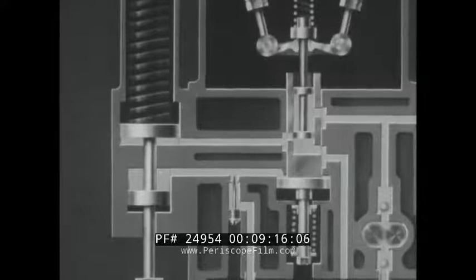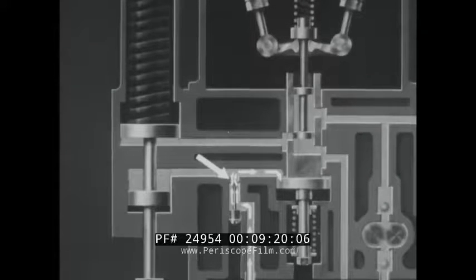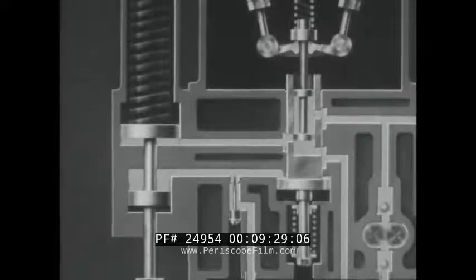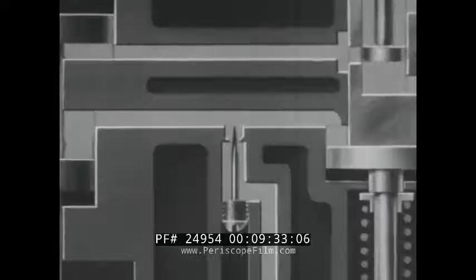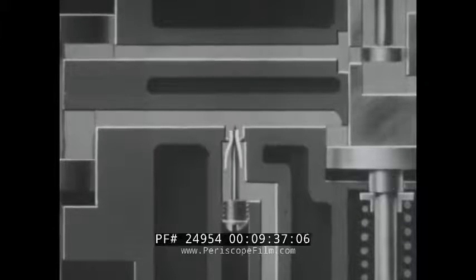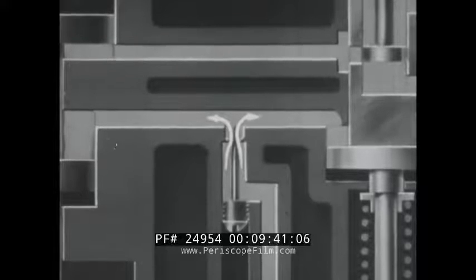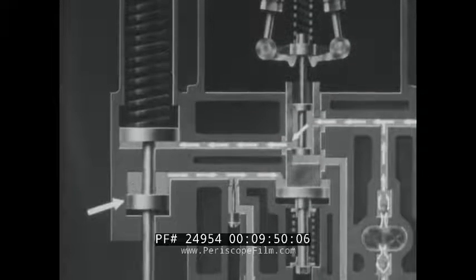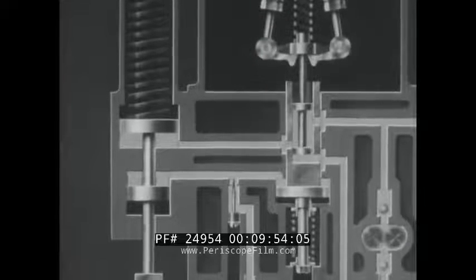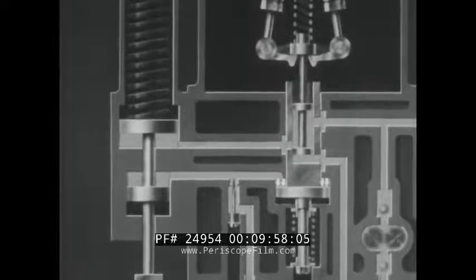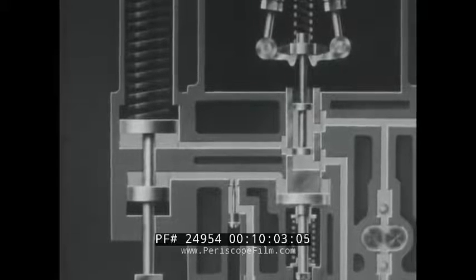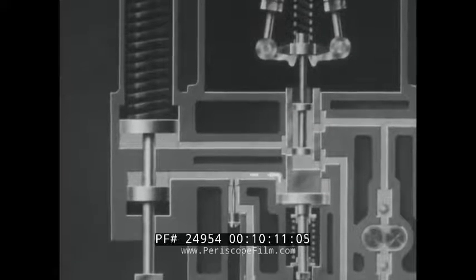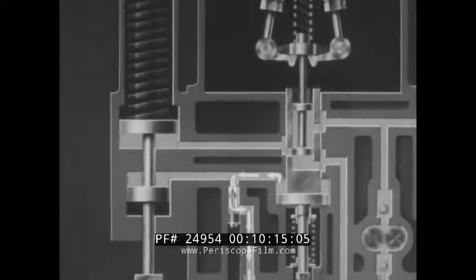As the flyweights and pilot valve return to their central position, oil flowing through a needle valve allows the compensating spring to return the pilot valve bushing to its central position. To keep the port closed, the bushing and plunger must descend at exactly the same speed. Therefore, the needle valve must be adjusted so that oil passes through at the required rate for the particular engine. When the engine speed drops below the set rate, the actuating compensating plunger moves upward with the power piston. This increases the oil pressure above the receiving compensating plunger, which therefore moves down, carrying with it the pilot valve bushing, closing the port leading to the power cylinder. The excess oil in the compensating system then drains out through the needle valve as the spring returns the bushing to its central position.